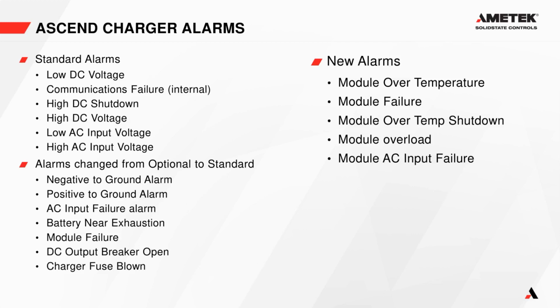Then we have a module overload alarm that indicates when one or multiple modules are in an overloaded state. And then we also have the module AC input failure alarm, which would indicate that some of the wiring inside the system has failed and one of the modules isn't receiving all 3 phases or the correct voltage.